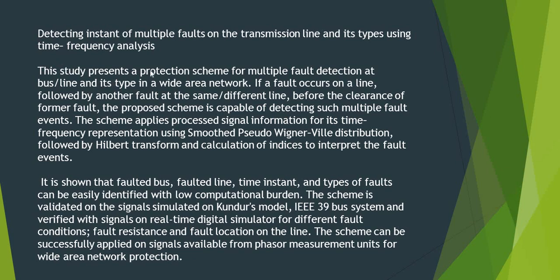This study presents a protection scheme for multiple fault detection at bus line and its type in a wide area network. If a fault occurs on a line followed by another fault at the same or different line, before the clearance of the former fault, the proposed scheme is capable of detecting multiple fault events. The scheme applies process signal information for its time frequency representation using smoothed pseudo-Wigner-Ville distribution followed by Hilbert transform and calculation of indices to interpret the fault events.